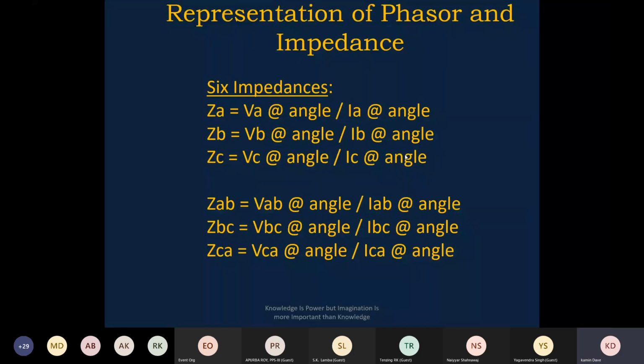So the manufacturer has given ZAB equal to VAB divided by IAB. That is fine. Then what has the 30-degree compensation to do with it? The second manufacturer has given VAB divided by IA. What has to be done with this? So one is the power system fault, and the second one is the relay algorithm. That has to be understood and evaluated according to the power system faults, and then the setting has to be done in the relay. Then I explained that your setting has to be this way, and only then will it cover your fault.